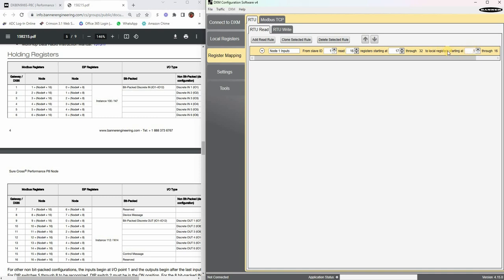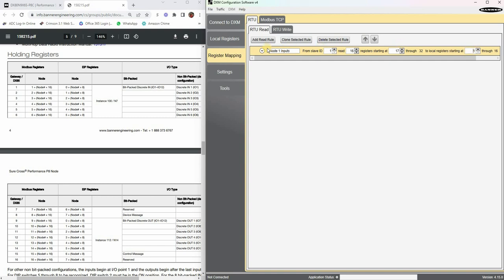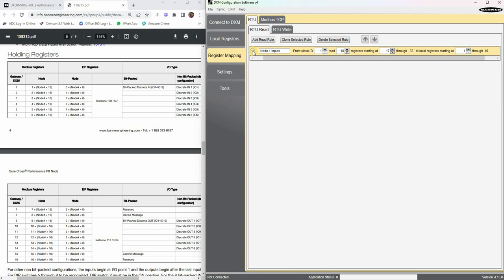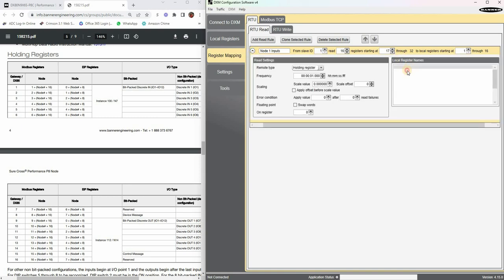And then this is the tricky part maybe for some people, to local registers. Basically what we're doing is like a kind of register copy. This is going to be an arbitrary number, I don't know, between one and like I think a thousand. You'll have to check the manual for what registers are allocated for 16-bit holding registers, but for the most part we could leave it at 17 so that it stays the same, but I'm actually just going to leave it at 1. And these are the values that my PLC is going to want to look at. This is what my PLC wants to communicate to over Ethernet. I've set that up. I don't need to make any changes there. When I give my registers names you'll see them populated up here.